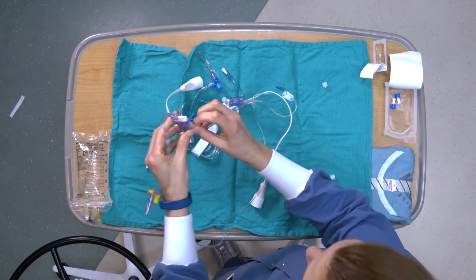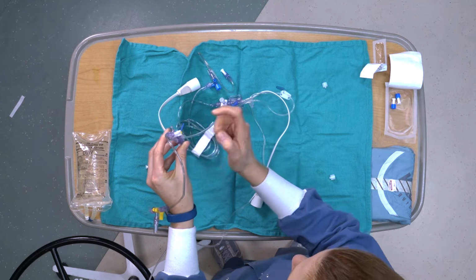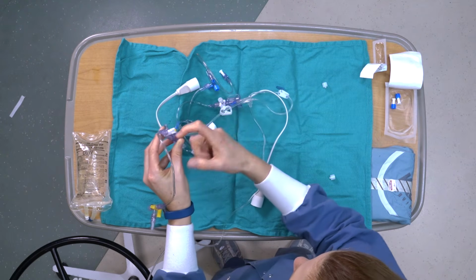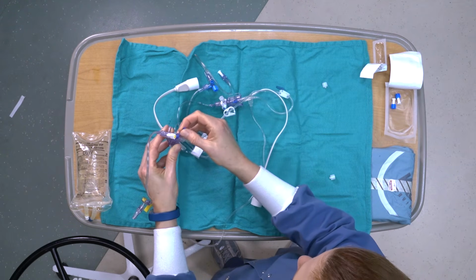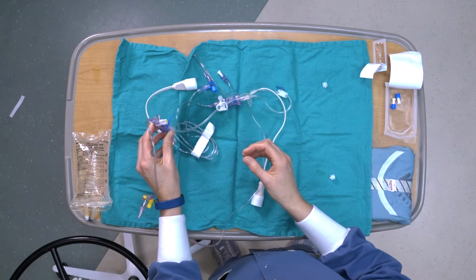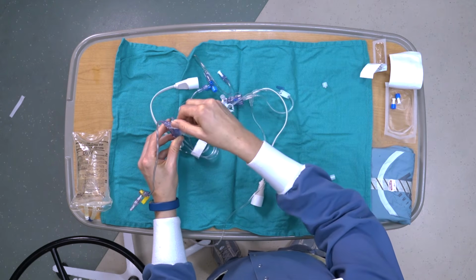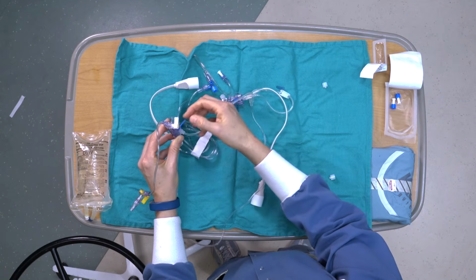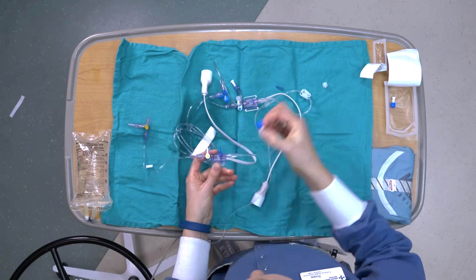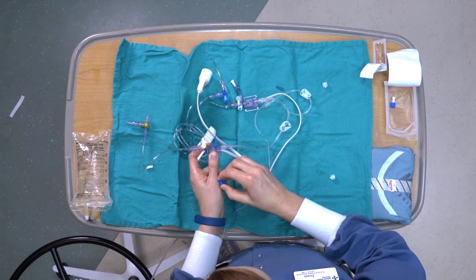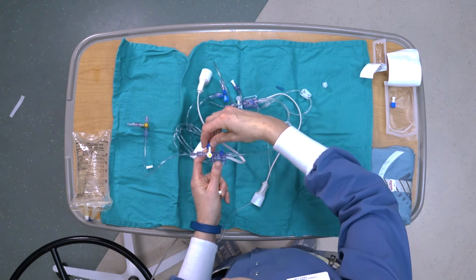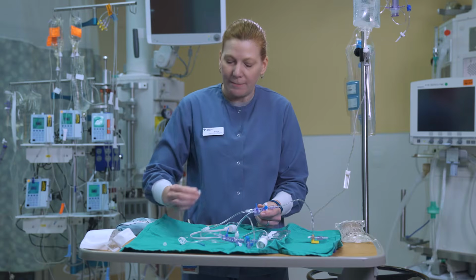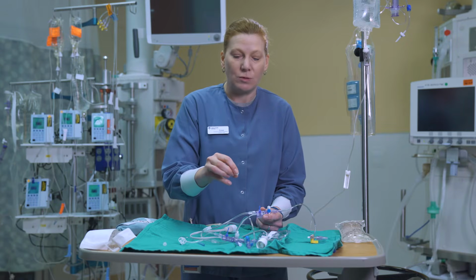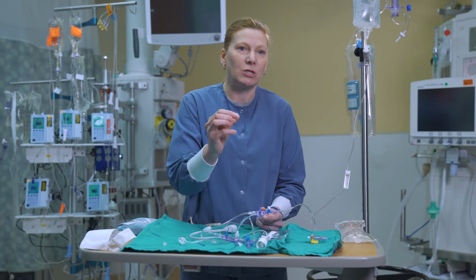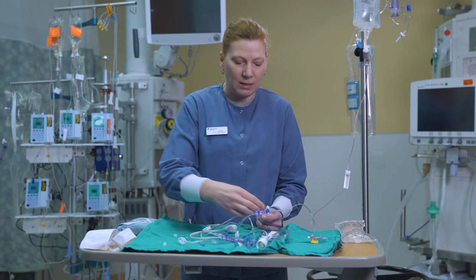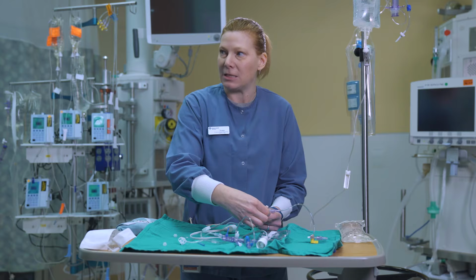Taking a look to make sure in the transducer that you don't see any bubbles, and if you do, you just give that a tap. Okay. Once you've flushed this through, we're going to turn that off. And we're just going to make sure that we put one of the blue completely blocked off caps on there. These smaller caps that usually come with the tubing actually have a hole in them. So we just want to make sure that we get rid of that and add the one that's going to keep that end sterile. Okay.